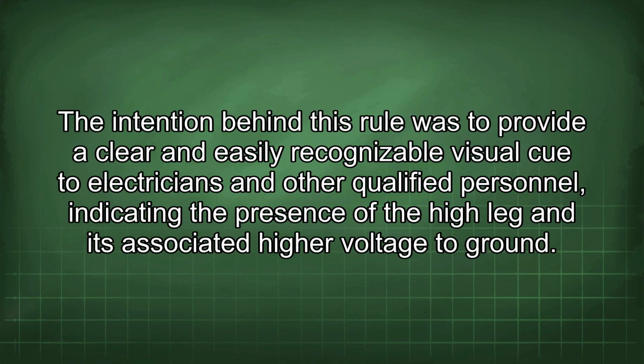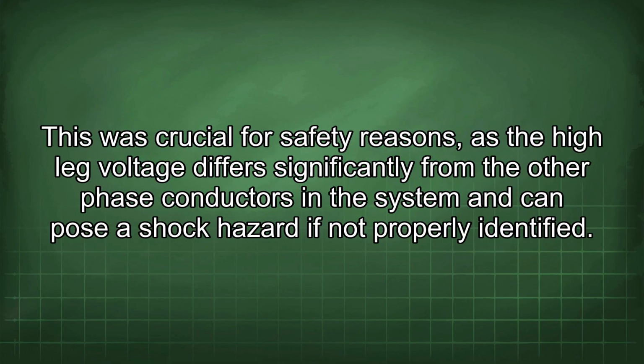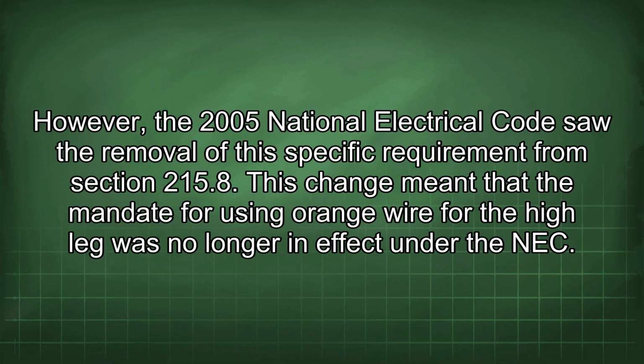The intention behind this rule was to provide a clear and easily recognizable visual cue to electricians and other qualified personnel, indicating the presence of the high leg and its associated higher voltage to ground. This was crucial for safety reasons, as the high leg voltage differs significantly from the other phase conductors in the system and can pose a shock hazard if not properly identified. However, the 2005 National Electrical Code saw the removal of this specific requirement from Section 215.8.